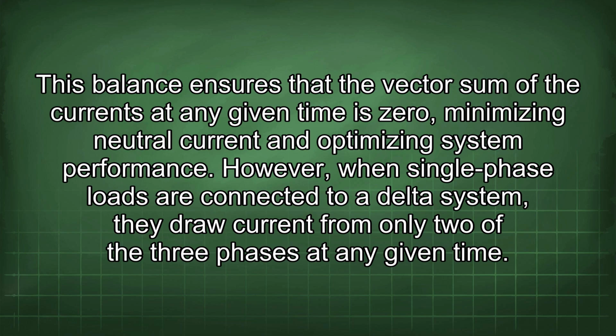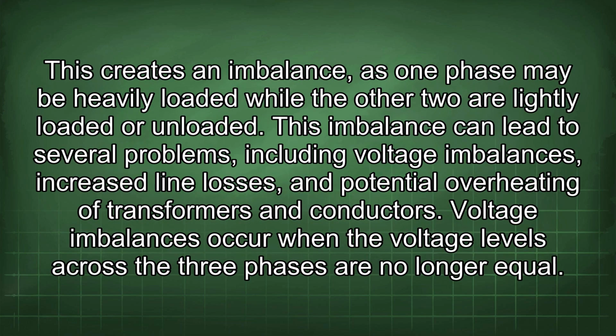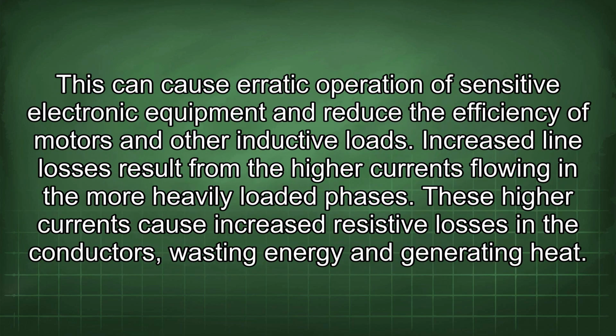However, when single-phase loads are connected to a delta system, they draw current from only two of the three phases at any given time. This creates an imbalance, as one phase may be heavily loaded while the other two are lightly loaded or unloaded. This imbalance can lead to several problems, including voltage imbalances, increased line losses, and potential overheating of transformers and conductors. Voltage imbalances occur when the voltage levels across the three phases are no longer equal. This can cause erratic operation of sensitive electronic equipment and reduce the efficiency of motors and other inductive loads.